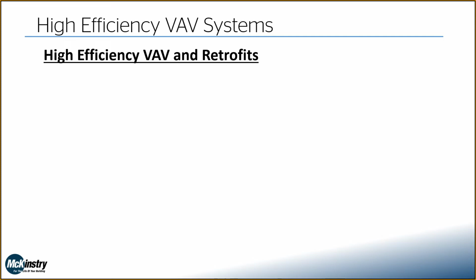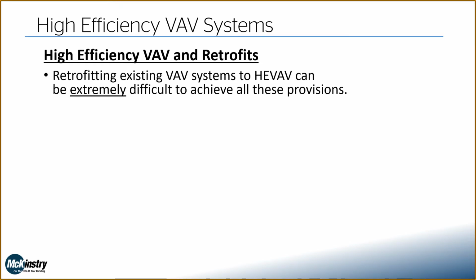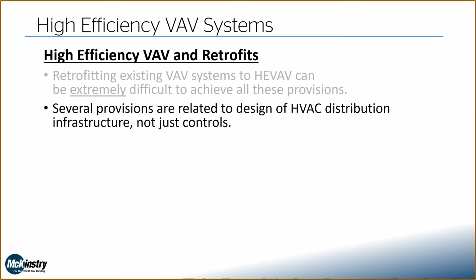So this is kind of near and dear to me because I mostly design for the energy group where we're doing retrofits all day, and we're looking at existing VAV systems, and the question often comes up, hey, can we turn this into a high efficiency VAV system? Ultimately, retrofitting these existing VAV systems can be extremely difficult to meet all 16 of those provisions. The main reason being several of these provisions are related to the design of the HVAC distribution infrastructure. So talking about ductwork especially, it's not just controls, which seems to be a common misunderstanding, that you just need to control it in an efficient manner.